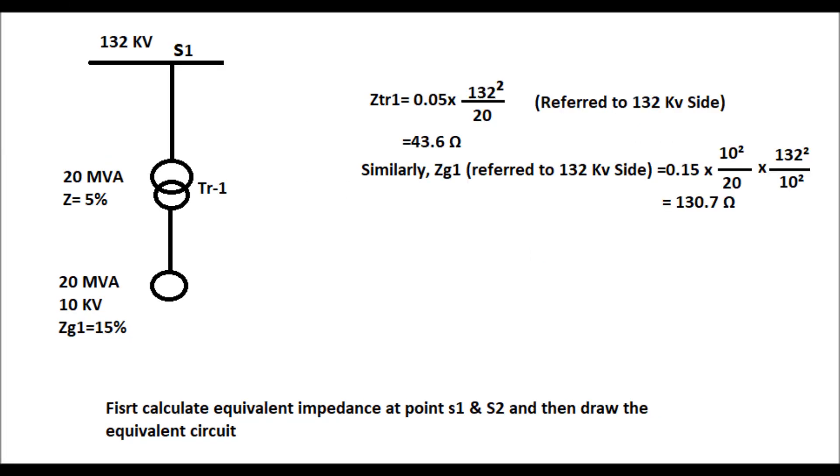First, we calculate the impedance at S1 which is referred to 132 kV side. For transformer, we know that the impedance Z is equal to percentage impedance times kV squared by MVA. By that means ZTR1 equals 0.05 times 132 kV squared by 20, that will come to 43.6 ohm.